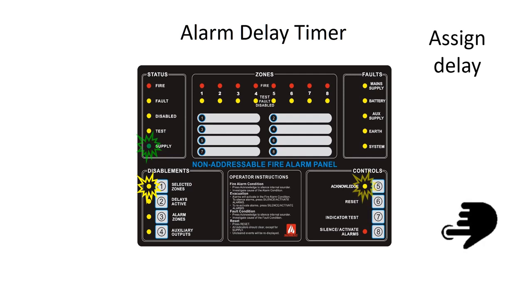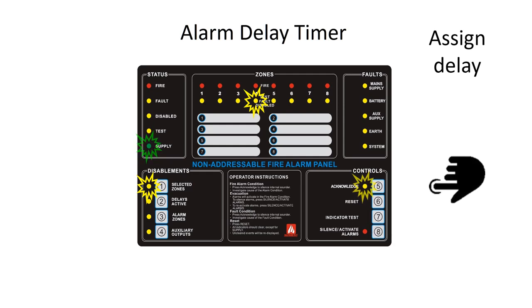Now, use the Silence Activate Alarms button to step through the detection zones. When the chosen detection zone is displayed, confirm the delay selection by pressing the Acknowledge button. The Selected Zones Fire LED will be on to show the selection.